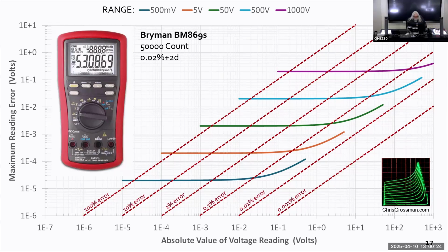Okay, and this is a very good meter, and you can see here, on most meters, they'll give you 0.02% of the reading plus 2 digits. Anytime you have a digital display, it's always plus or minus 1 digit on the last digit. So they specify plus or minus 2 digits. Let's say here we're on the mid range, which is the 50-volt range, and we're measuring 10 millivolts. That's a 10% error of it. The key thing on all of these is the meter's most accurate toward the top end of the range it's measuring at.